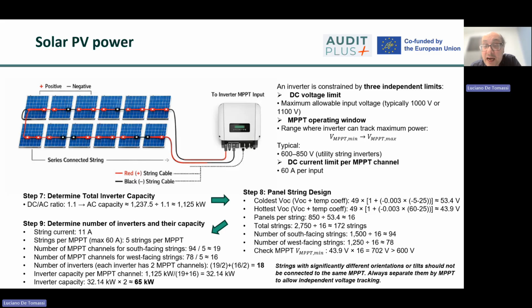Panel string design involves configuring how individual PV modules are electrically connected in series and in parallel to match the operating voltage window of the inverter. Each inverter has a defined MPPT, maximum power point tracking voltage range, and maximum DC input voltage, and the string design must ensure that the combined voltage of modules stays within these limits under all temperature conditions.